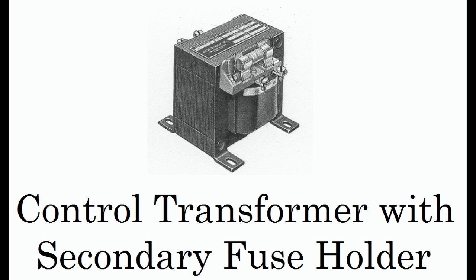Notice that the transformer has two primary windings. These are usually each rated at 240 VAC. By connecting them in parallel, we obtain a 240 VAC primary, and by connecting them in series, we have a 480 VAC primary.